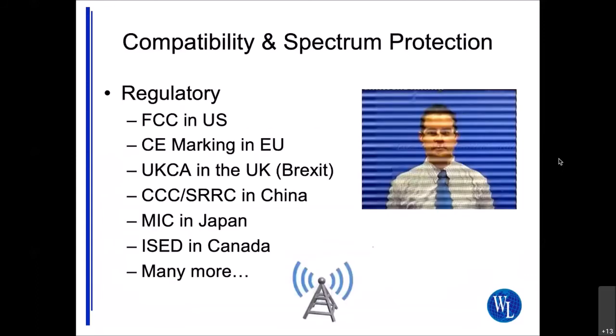As I mentioned, regulatory requirements have driven a lot of these things, at least in my career. We have the FCC, we have CE marking in the European Union, and we have something called UK Conformity Assessed in the UK, which came out of Brexit. Since the beginning of the year, there's been a transition period for manufacturers to apply the UK CA mark, which is pretty much the same technically as CE marking. Because the UK is no longer in the European Union, as of the end of this year you'll have to apply the UK CA mark to your device if you plan to sell it in the UK.